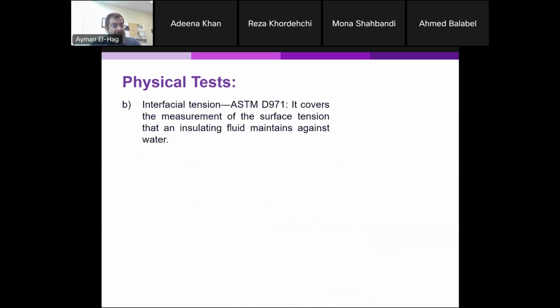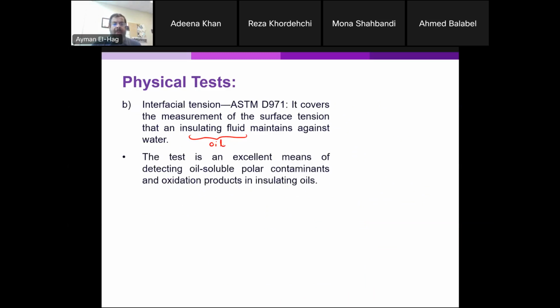Second test is the interfacial tension. And this is covered by ASTM D971. Now, it measures the tension of an insulating fluid, which in our case is transformer oil, against water. Okay. So let's see how we do the test, and then we'll talk about what it really means. Okay. So first, it is basically a very good means to detect any oil-soluble polar contaminants or any oxidation products.